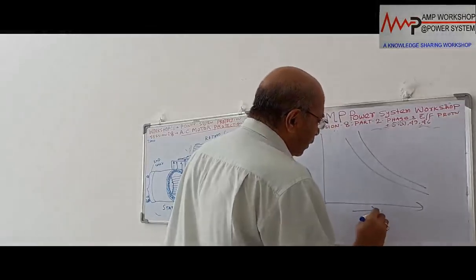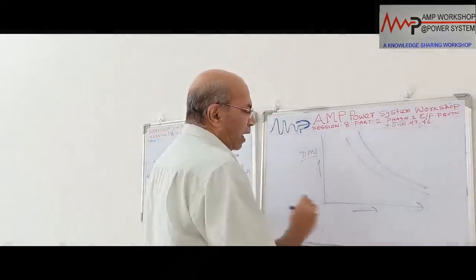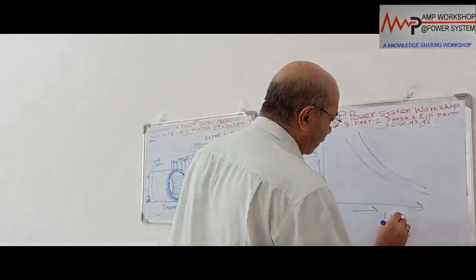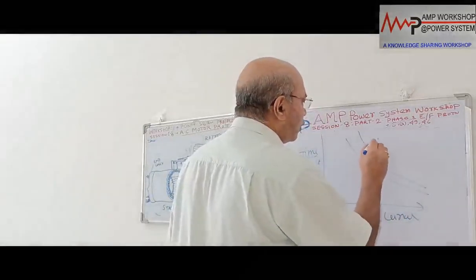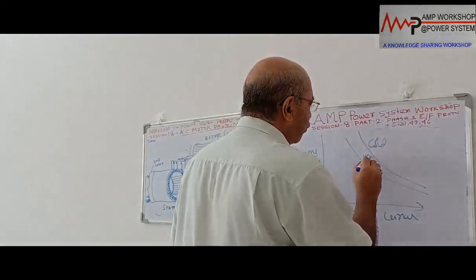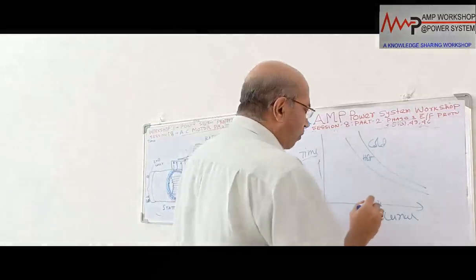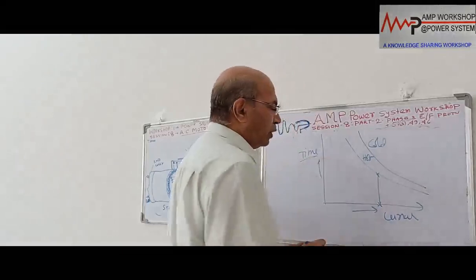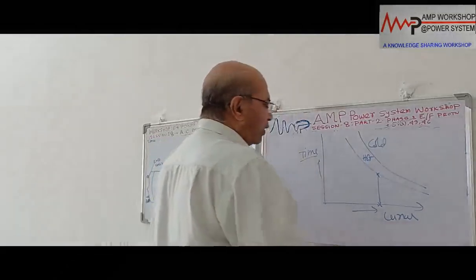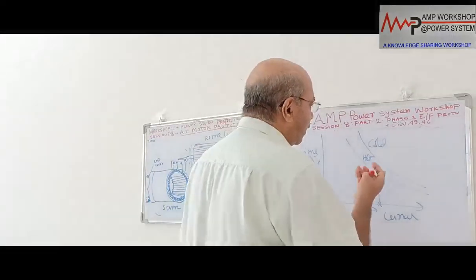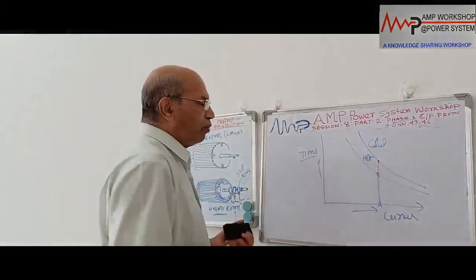This is the withstand time. This is time. Okay. And this is the corresponding current. So this shows that this cold curve is always above the hot curve, because when the motor is hot, it can withstand less time. For a particular current, suppose this is the current, the motor withstand time is this if the motor is hot. But if the motor is cold, then the withstand time will be more than this. For this same current, if the motor is in cold condition, meaning the motor is not running, then the withstand time will be like this. So this is the motor withstand time.